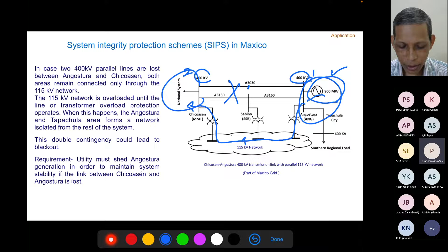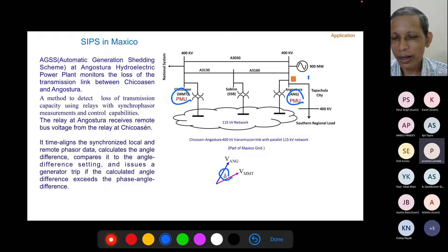So they put two PMUs at two locations, and at one control center they provide the corresponding PMU data in real time, so the angle between the voltages on these two sides is available in real time. If the corresponding angle increases beyond about 10 degrees as per this data, then the generation side has to be reduced substantially, and the system can be maintained. So even when the double circuit line is not there, the network's integrity can be maintained.